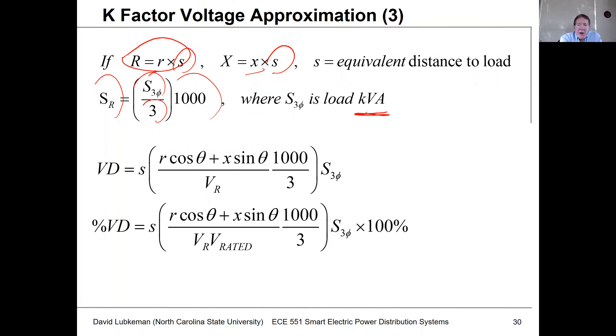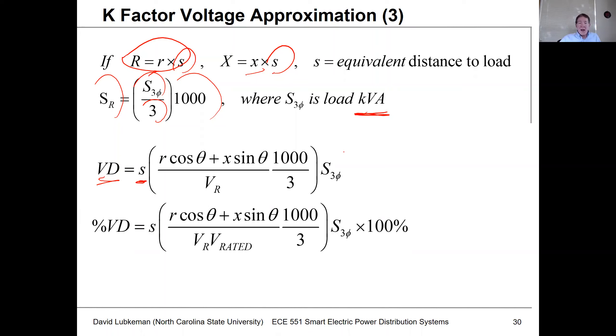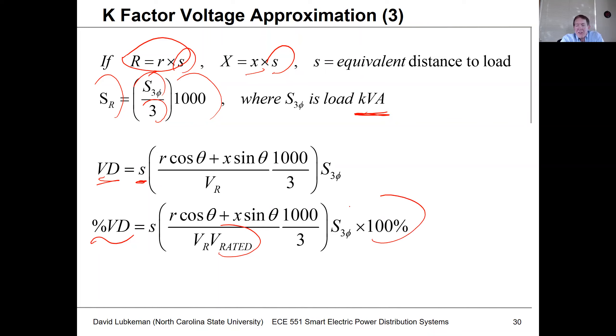When we break the net resistance and reactance into a line length times an equivalent resistance and reactance per unit length, the voltage drop becomes the equivalent line length times the quantity (r cosine theta plus x sine theta) over VR, times 1,000 over 3, times S3-phase. To normalize in terms of percent voltage drop, we divide by the nominal line-to-neutral voltage V-rated and multiply by 100%.